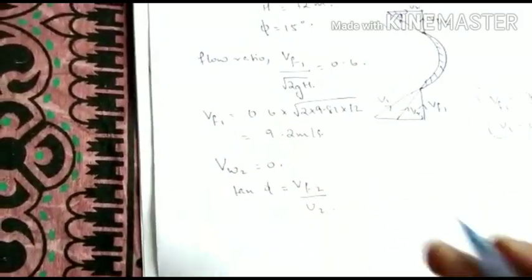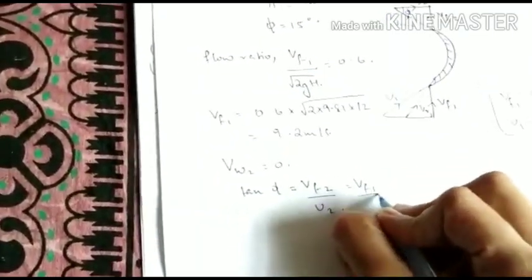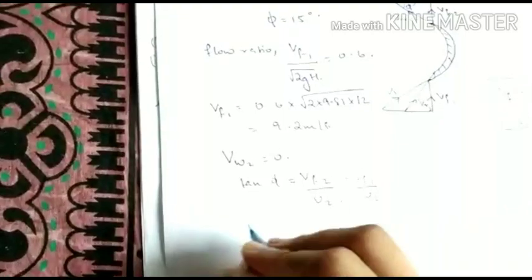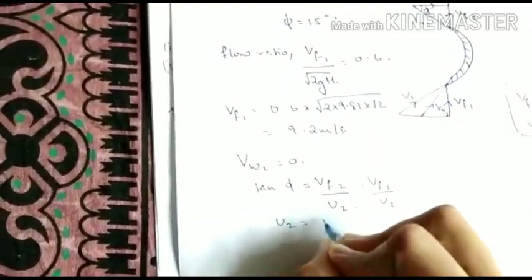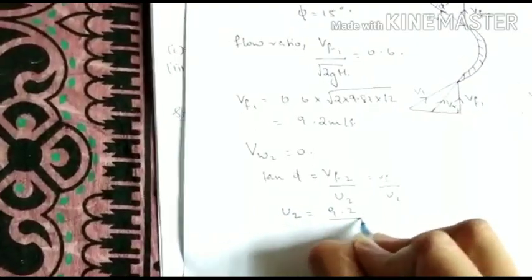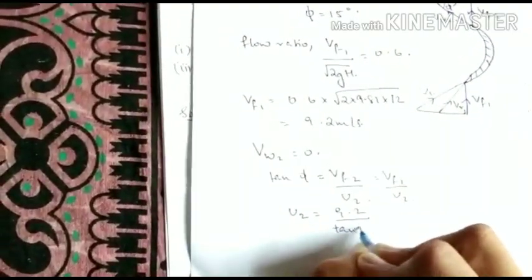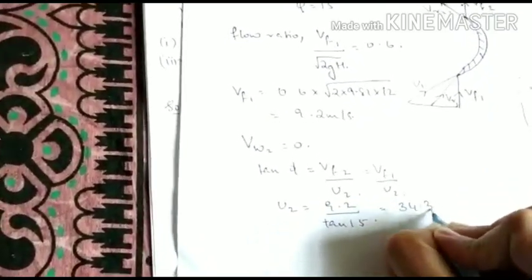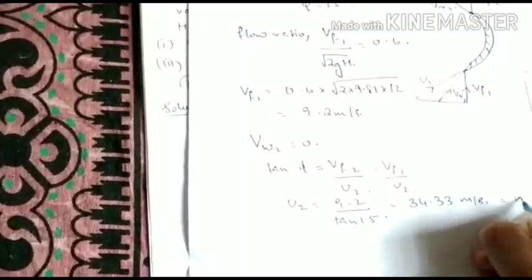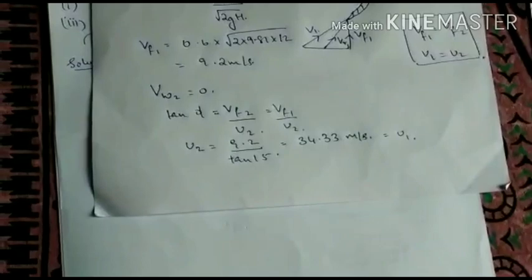VF2 is given because it is same as VF1. So from that you can find U2: 9.2 divided by tan 15. And you will get it as 34.33 meters per second. U2 is equal to U1 for Kaplan turbines.